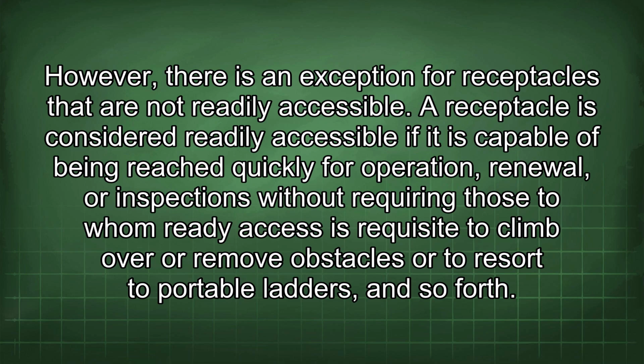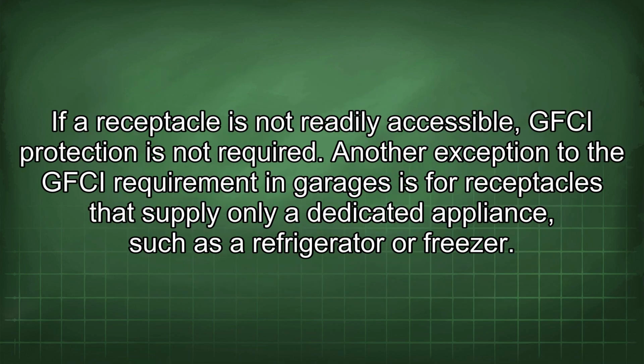A receptacle is considered readily accessible if it is capable of being reached quickly for operation, renewal, or inspections without requiring those to whom ready access is requisite to climb over or remove obstacles or to resort to portable ladders, and so forth. If a receptacle is not readily accessible, GFCI protection is not required.